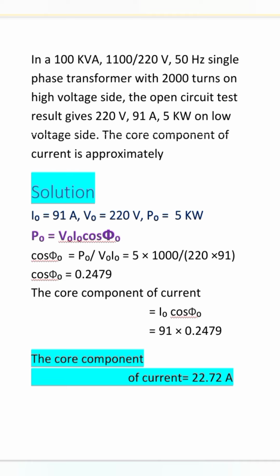We know the formula of the core component of current is equal to I0 cos phi0. They give the I0 value as 91 amps. Then we need only cos phi0. We can calculate cos phi0 from P0. Substituting P0, V0, I0, we get cos phi0. And substituting cos phi0 and I0, we get the core component of current is equal to 22.72 amps.